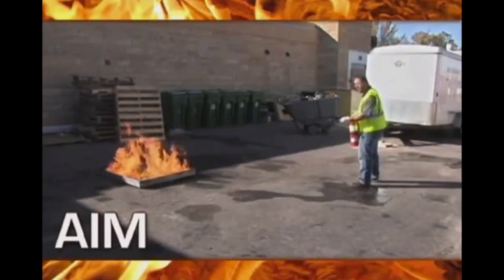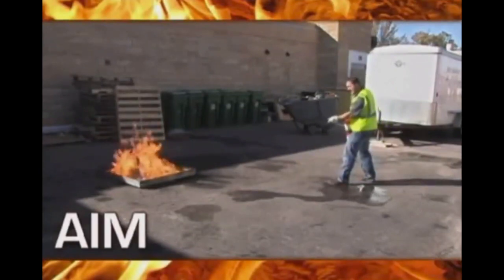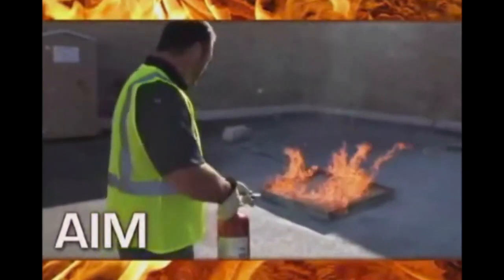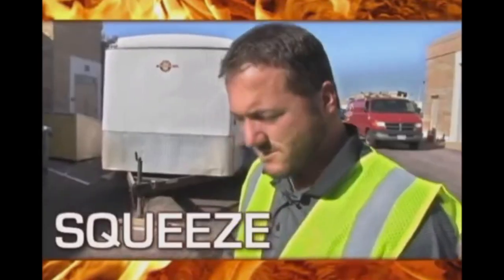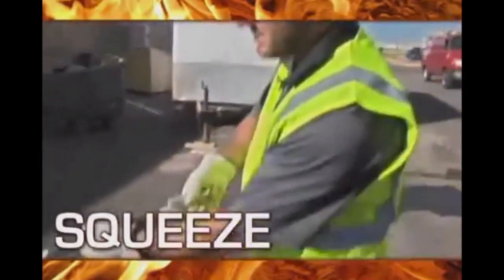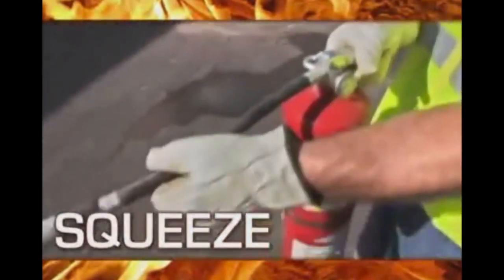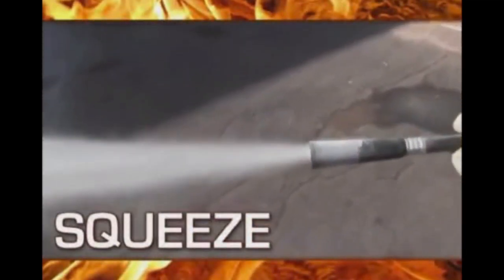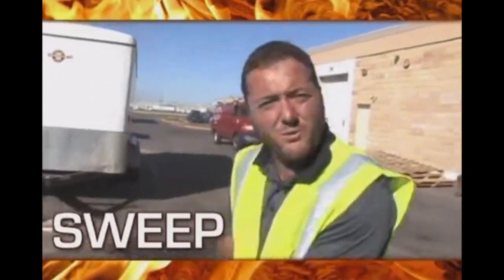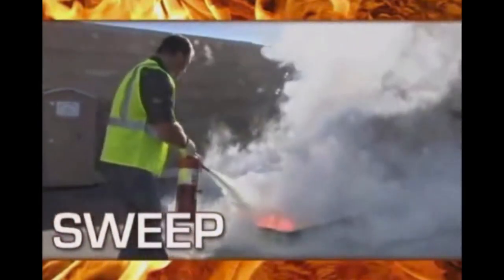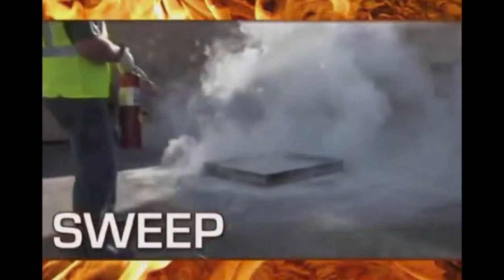Grab this nozzle, and we're going to aim at the base of the fire, staying a nice safe distance away. And S is for squeeze. When we squeeze this handle, we'll discharge the unit. And the last thing we're going to do is sweep. We're going to sweep at the base of the fire and try to put out the flames from the bottom up.